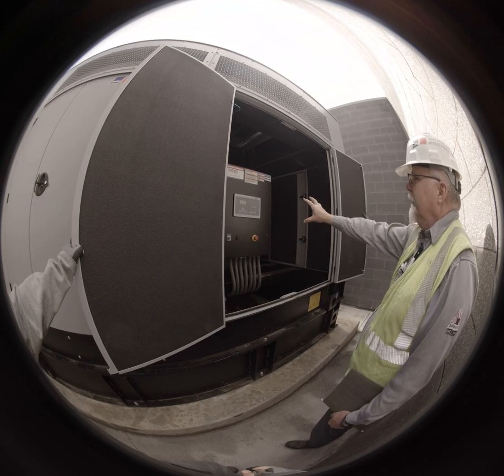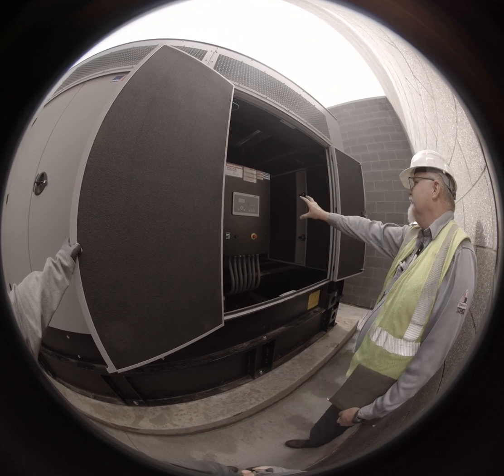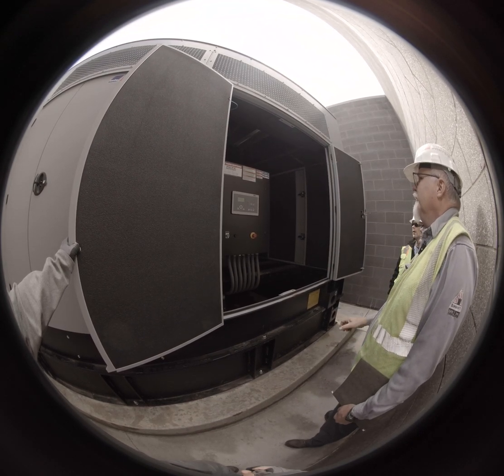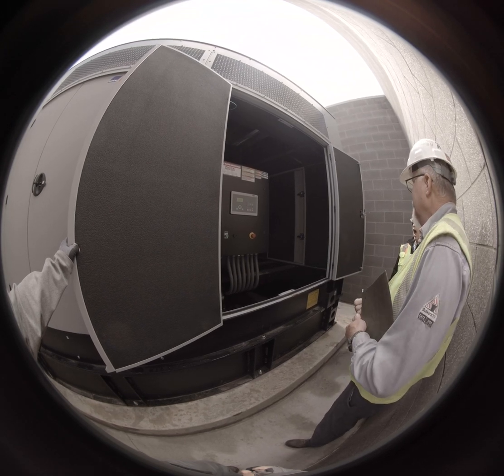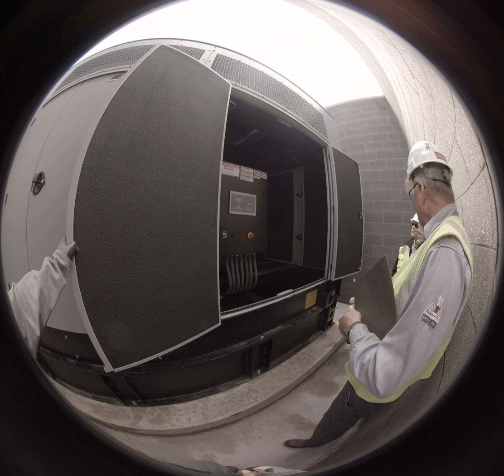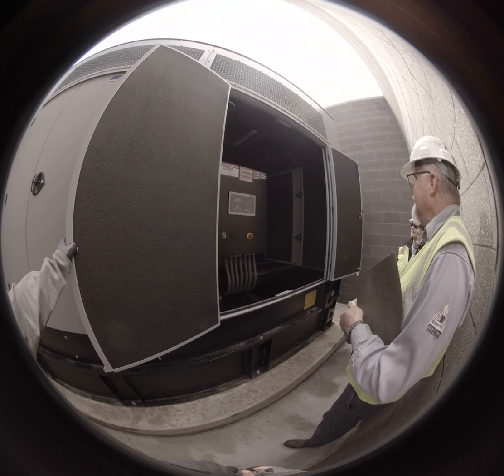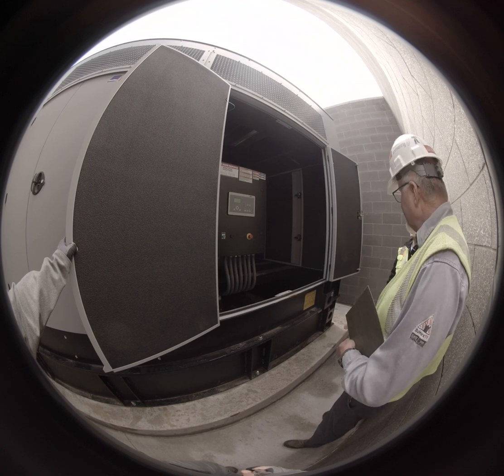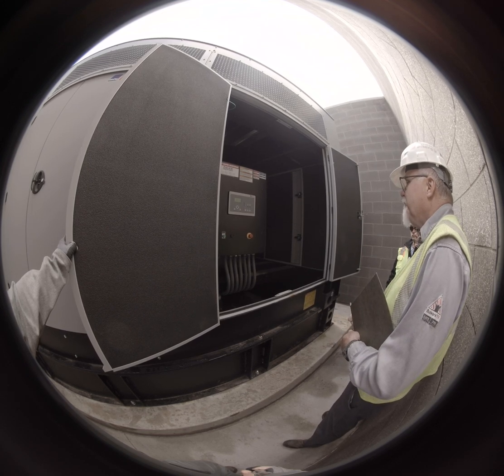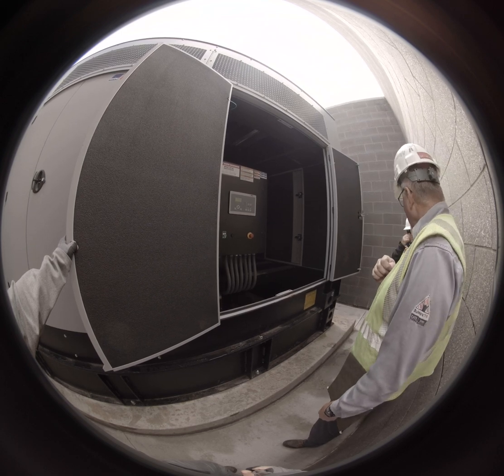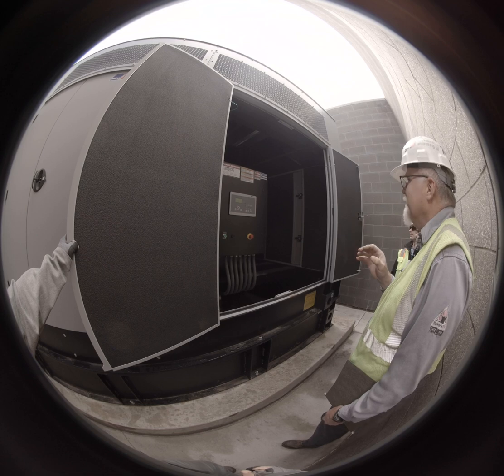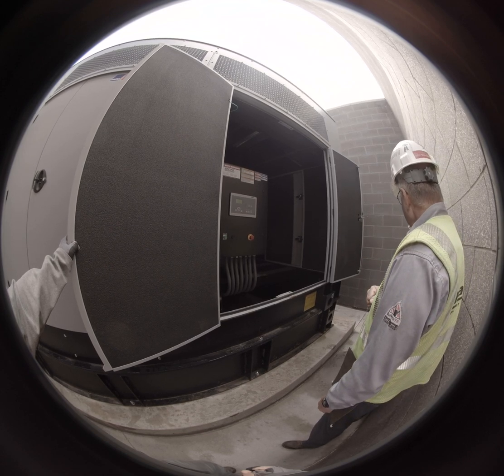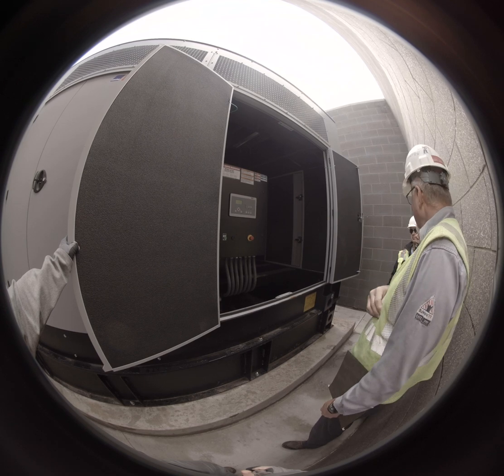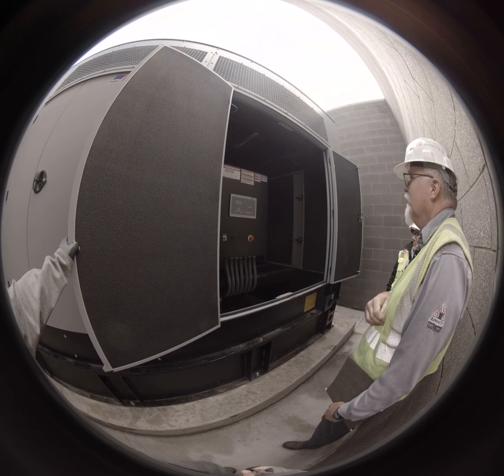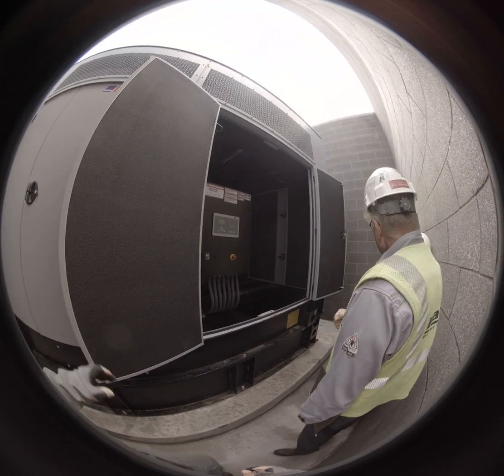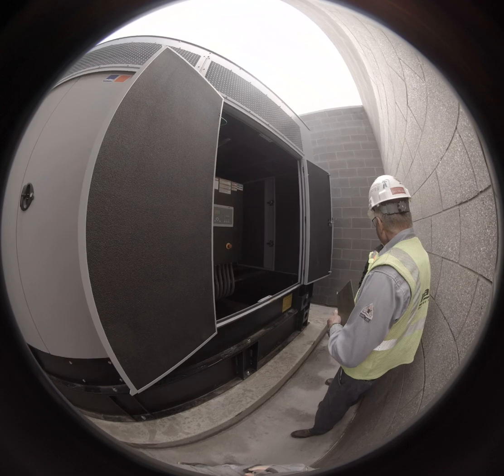With the ECM, we have what we call the MGC control panel. The MGC control panel not only monitors engine parameters, it also monitors all of the electrical parameters and the run logs, how much load's on it, all of that stuff. You can basically spend a day going through this thing. The one thing I will tell you about this is as long as you do not punch in the access code, you can do whatever you want. Can't change it. That's important. So within this control, we have two sets of parameters. We have metering and we have settings.